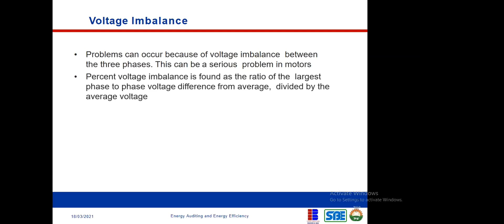Okay. So problems can occur because of voltage imbalance between three phases. Now, voltage imbalance is basically a problem of three-phase systems, not single phase. This can be a serious problem in motors. It really affects the operation of motor systems. Percentage voltage imbalance is found as the ratio of the largest phase to phase voltage difference from the average. Now you have to divide by the average voltage.